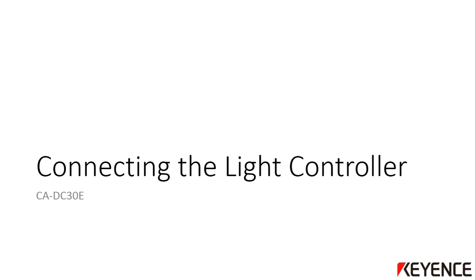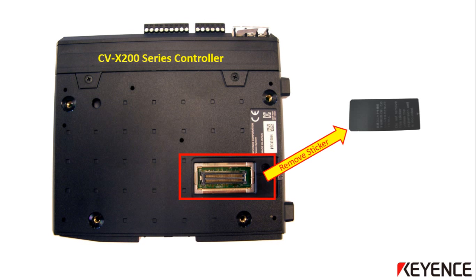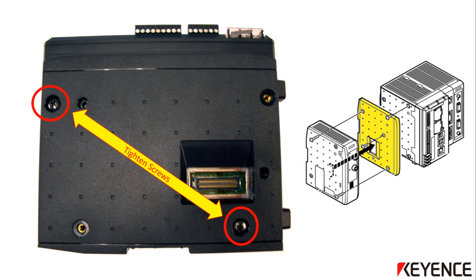The next section will cover how to connect the light controller to the main CV-X vision controller. The first step is to remove the sticker that covers the light controller connection on the left side of the main CV-X200 series controller — on the same side as the I/O connections and the power terminals. You can discard this sticker. The next step is to affix the plastic spacer included with the CA-DC30E light controller. Align it on the side of the CVX controller and tighten the two screws indicated here in red. The spacer is required, or the light controller will not mount correctly and will fail.